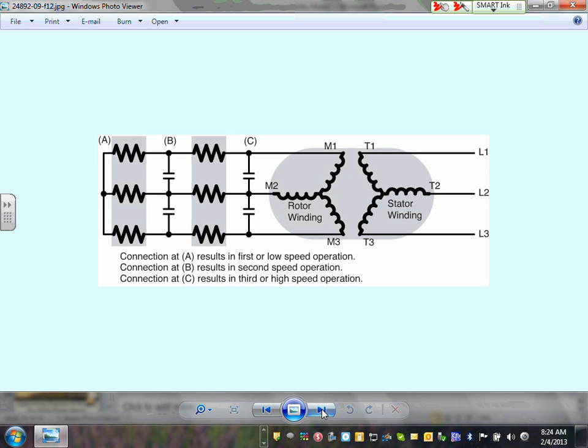and a bank of resistors, the more resistors you put in, the slower the motor will be. When you shunt all these resistors together, when you close them, the motor will run as an induction motor. So when you start your motor, guys, all these resistors are in the circuit, so it starts slowly, gently, with good torque. Then when it's up and running, you shunt these to control your torque.